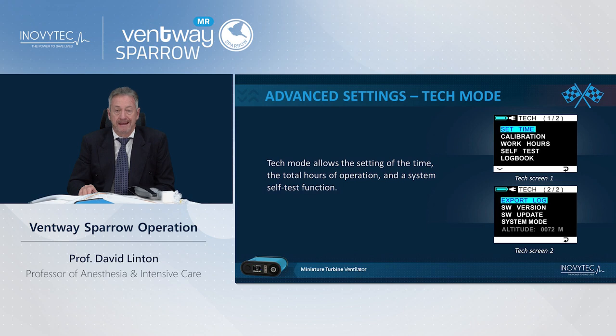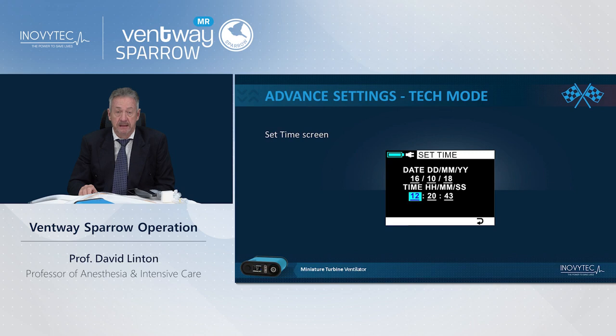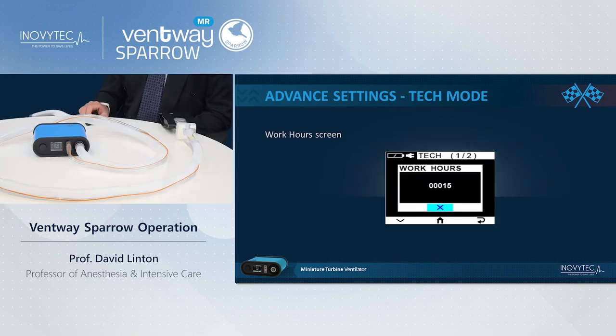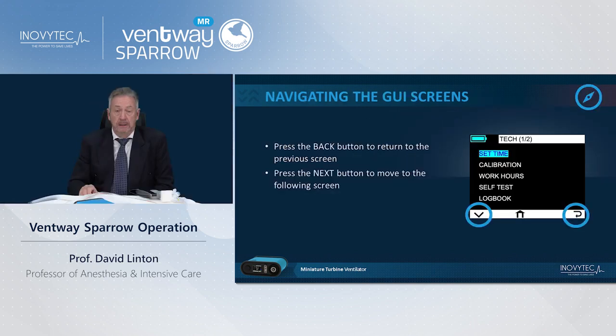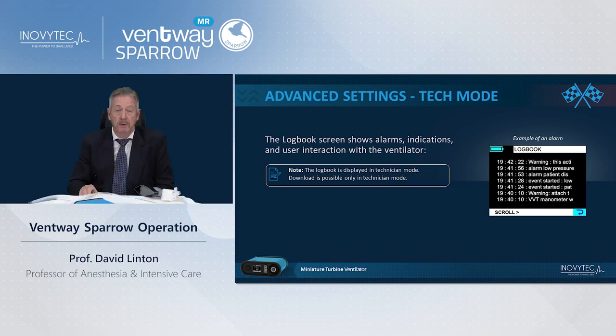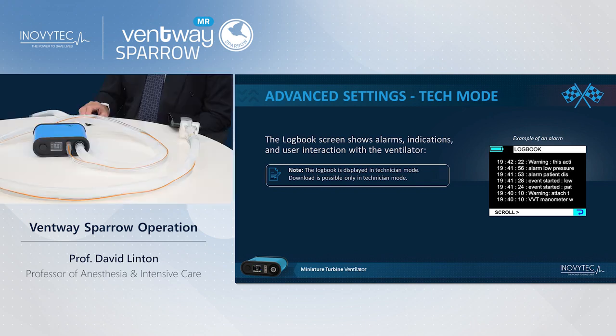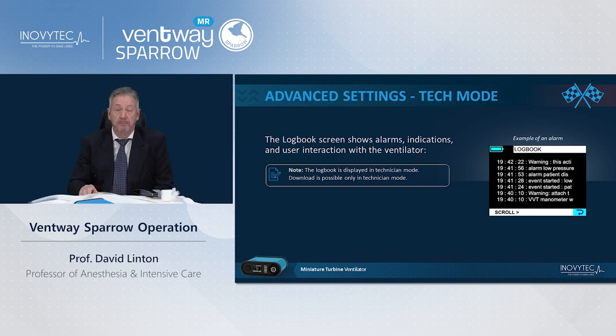When you select in the advanced settings the technical mode, it gives you the option to adjust many parameters of the ventilator in terms of setting the time and date, as you would do on any computer or mobile phone. It tells you the working hours of the ventilator, and if you want to change the screen to the next screen in the technical mode, you will see in the bottom left-hand corner the indicator to go down to the next screen. If you select logbook, it will give you the indication of the alarms that occurred and the user interaction with the ventilator that occurred. This is all recorded and can be downloaded by USB to a computer for evaluation.